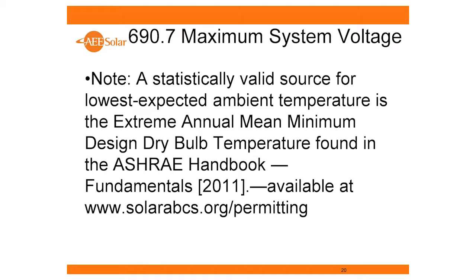The 2011 code added this stuff about maximum system voltage and using ASHRAE data rather than all-time lows for that. And that was really to address the fact that especially in colder climates, which some in the room deal with, we're getting people having much too conservative voltage calculations on your PV systems, which is causing PV systems not to operate well in the summertime.